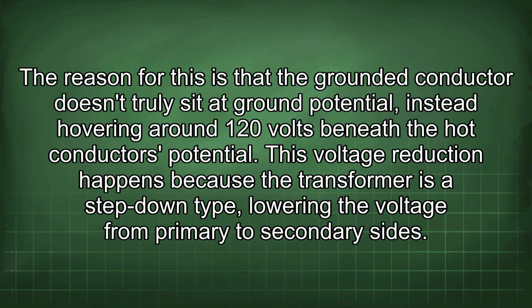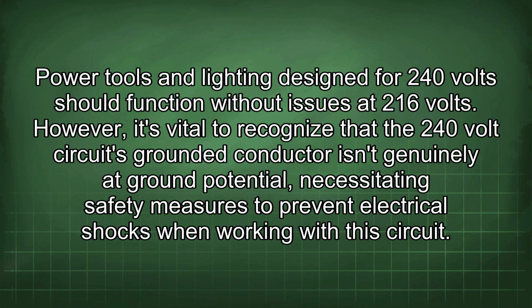The reason for this is that the grounded conductor doesn't truly sit at ground potential, instead hovering around 120 volts beneath the hot conductor's potential. This voltage reduction happens because the transformer is a step-down type, lowering the voltage from primary to secondary sides. Power tools and lighting designed for 240 volts should function without issues at 216 volts. However, it's vital to recognize that the 240-volt circuit's grounded conductor isn't genuinely at ground potential, necessitating safety measures to prevent electrical shocks when working with this circuit.